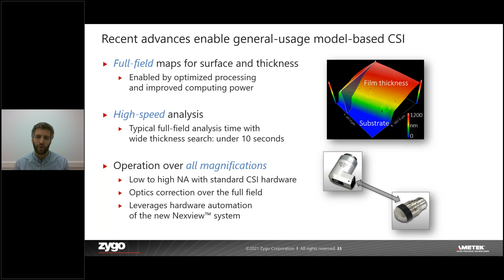So fortunately, recent advances have enabled us to solve those problems and to provide general usage model-based CSI that creates full field maps of both surface topography and thickness across the entire camera array in less than 10 seconds for typical measurements and over the full range of objective magnifications. So that's from the very low mag 1x objective wide field of view up to the 50 or 100x magnification to view those very small features and very fine surface topography. And this model-based CSI leverages the hardware automation of the Nexview and the Nexview NX2 platform, and so is only available on those systems.